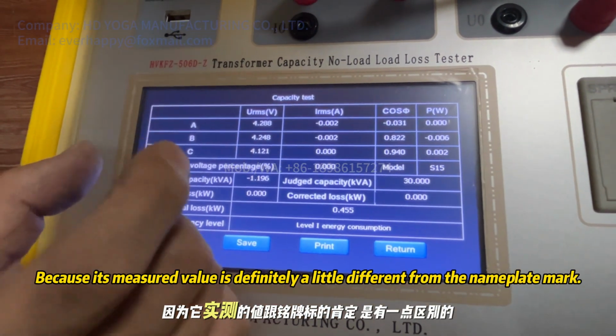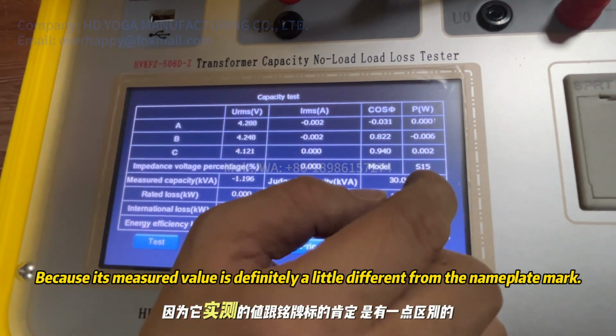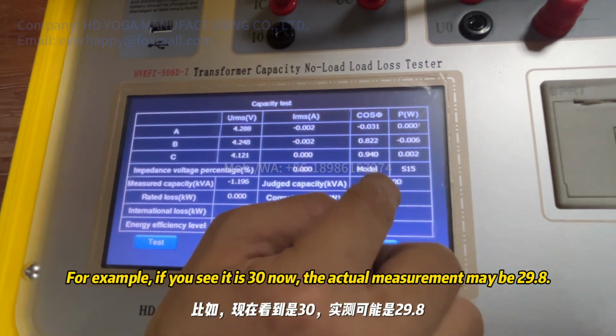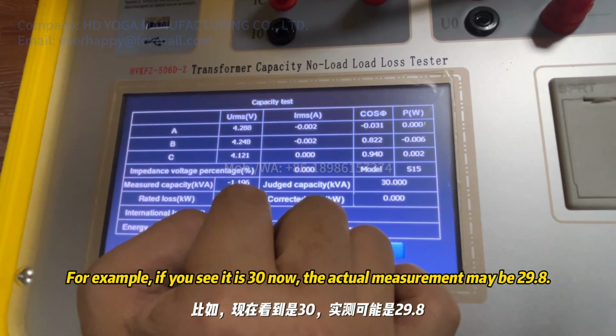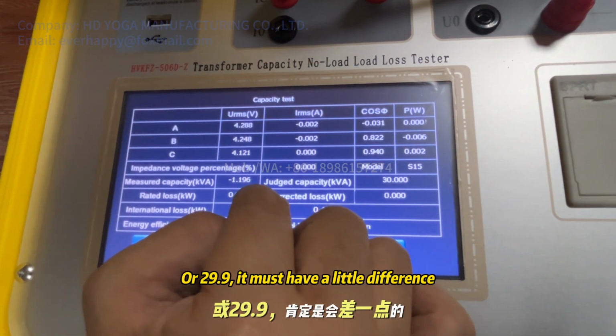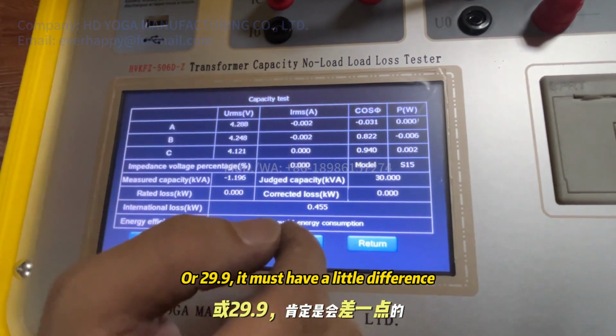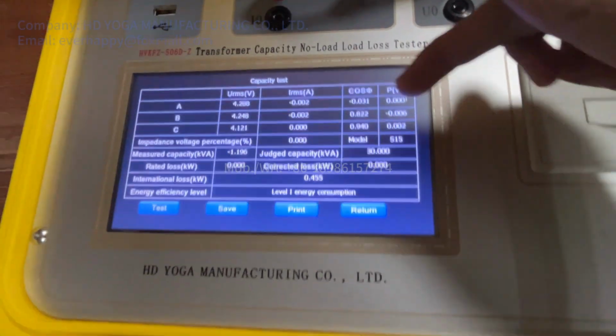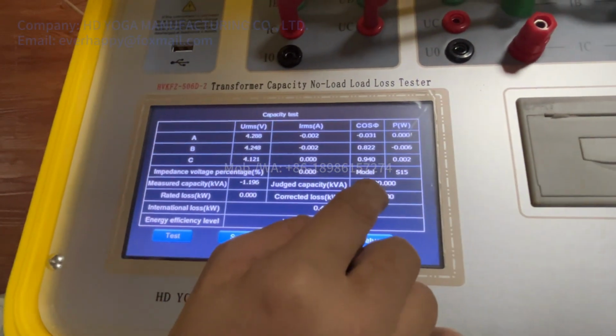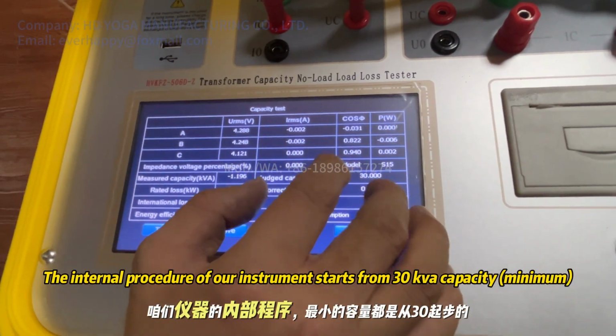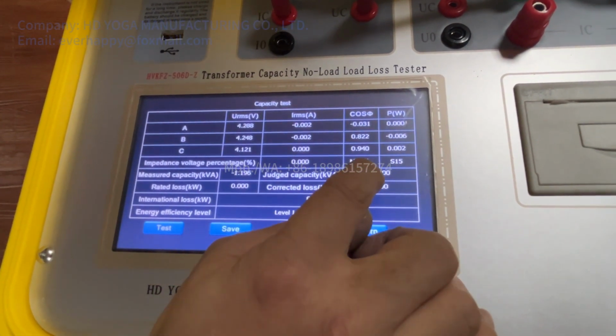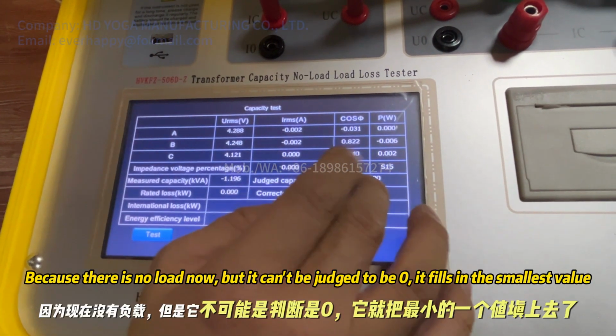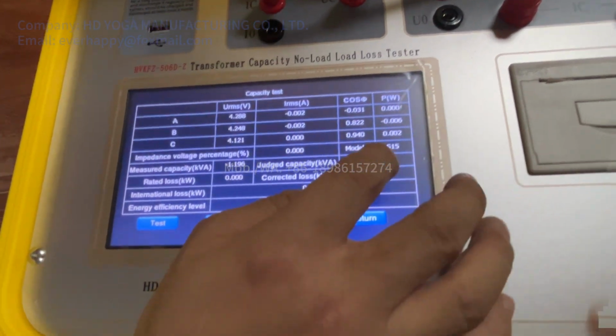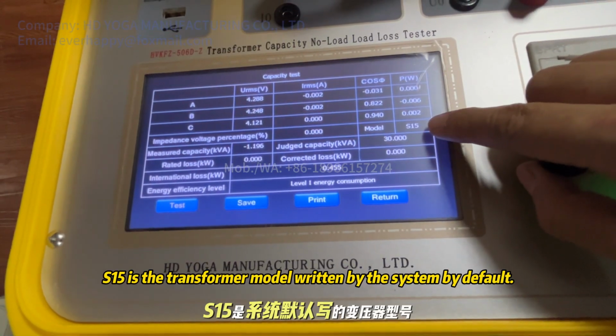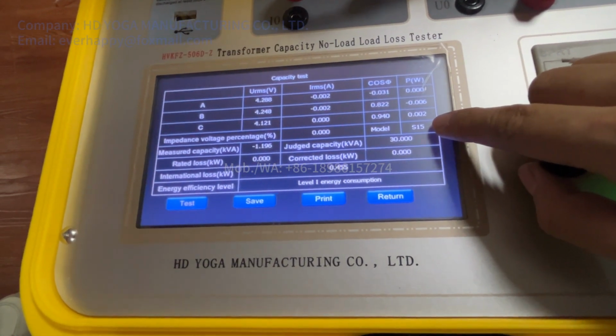Because its measured value is definitely a little different from the nameplate mark. For example, if you see it as 30 now, the actual measurement may be 29.8 or 29.9, it must have a little difference. Because there is no load now, so this value is negative. The internal procedure of our instrument starts from 30 kVA capacity minimum, because there is no load now, but it can't be judged to be 0, it fills in the smallest value. S15 is the transformer model written by the system by default.